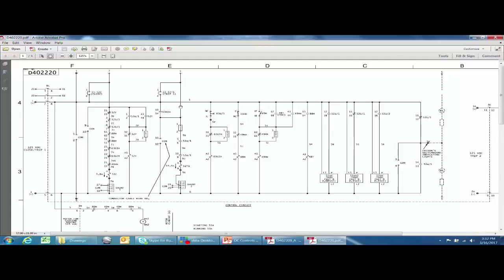What do you do with the circuit breaker if you're running out of gas? There are two schools of thought on low gas conditions. One is that you block trip — you've already blocked close, so essentially you're blocking all breaker operation. The other school of thought is that you block close and then trip, and that's how this utility does it. Once you have gone to a low gas condition and the auxiliary relay picks up, you're going to trip the circuit breaker with that contact.